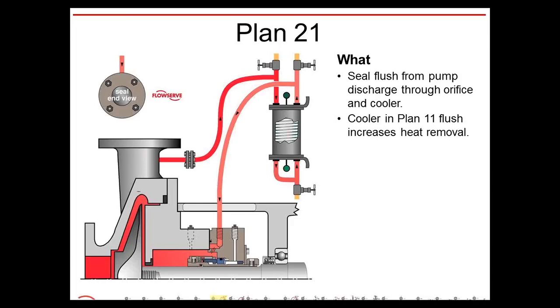It would be much more advantageous just to exchange a small area, just what's in the seal chamber itself, with the exchanger and cool that fluid down. It's much more efficient, and it's much easier to do than to constantly take hot fluid and cool it down.